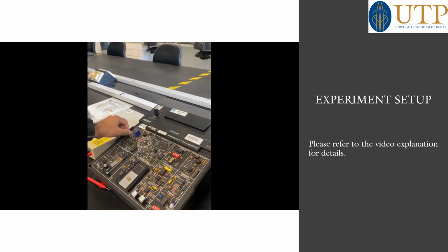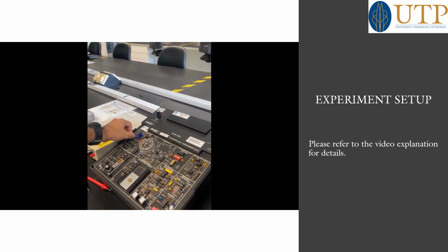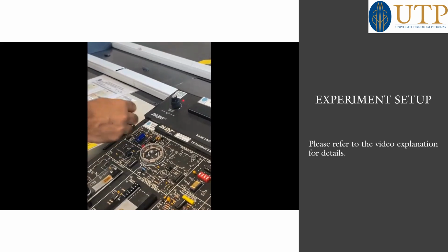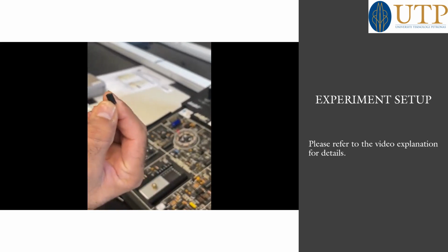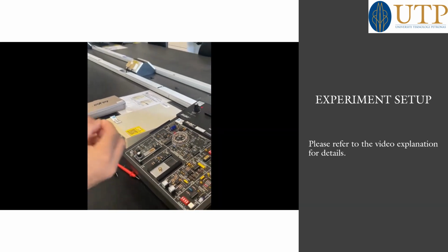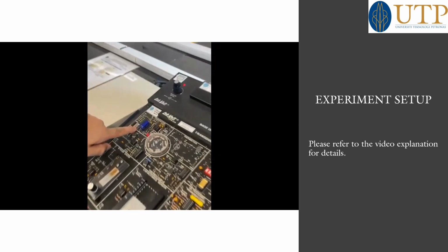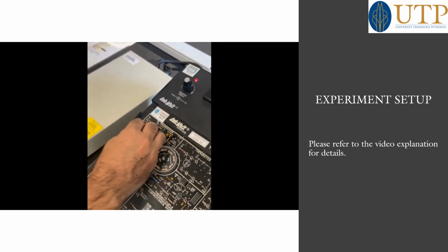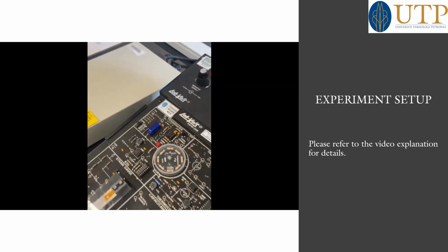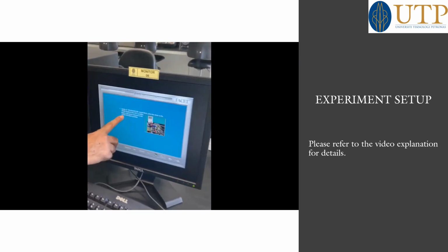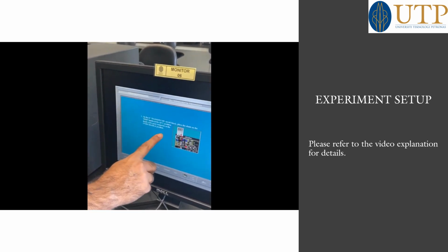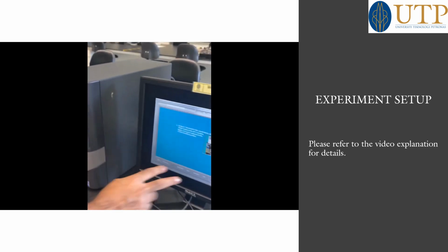Now you see on the IC transducer circuit block, place the shunt on the temperature header in the 40-degree position. This is called a shunt. What he said is to place the shunt at 40 degrees. The default temperatures are 35, 40, 45 and 50. Where I have to place it is at 40 degrees. And what he says again is, insert a 2-post connector in the oven enable position.